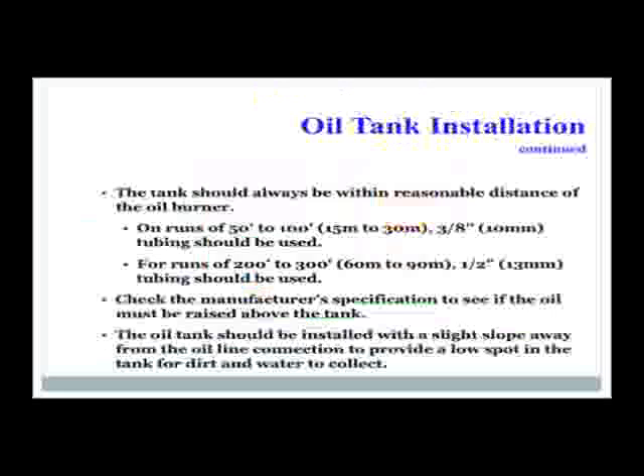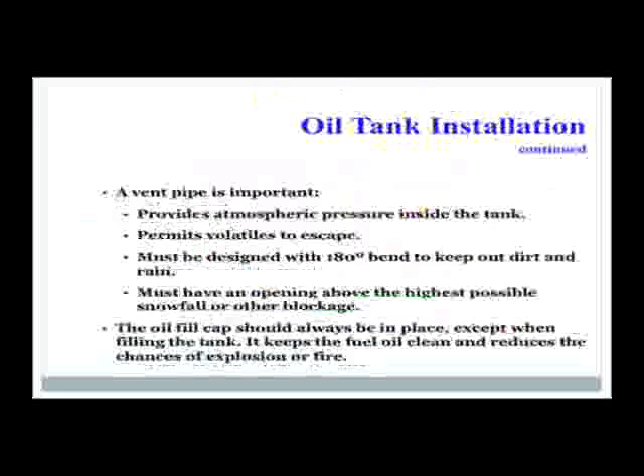Oil tanks should be installed with a slight slope away from the oil line connection to provide a low spot in the tank for dirt and water to collect. A vent pipe is also important. It provides atmospheric pressure to inside the tank. It permits volatiles or gases to escape, and it must be designed with a 180-degree bend to keep out dirt and rain. It must have an opening above the highest possible snowfall or any other blockage. The oil fill cap should always be in place except when filling the tank. This keeps the oil clean and reduces chances of explosion or fires.